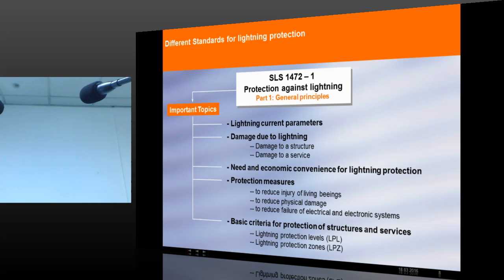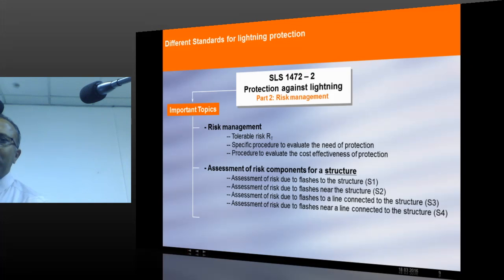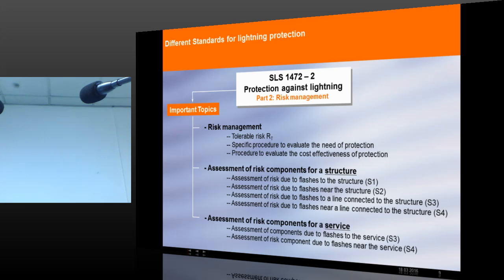Lightning current parameters means basically it starts with how much energy is involved during a lightning. What is the shape of the current? In how much time it is going from 0 to peak, and in how much time it is coming to 0 or maybe half. The basic parameters of lightning current are explained with respect to the strength of current from how many kiloampere to how many kiloampere, and the wave shapes are explained. And in case of a strike in a normal building, what can happen to a structure, what will happen to a service, and detailed analysis is given. But what is important for you is the last 2 points, lightning protection zone as well as lightning protection level. Lightning protection level is explained in the standard for the purpose of making a risk assessment, or to ensure that you are able to find out the risk involved in lightning in your building.